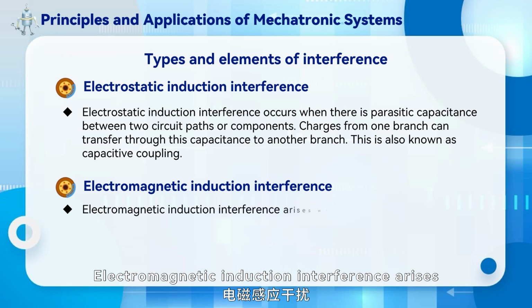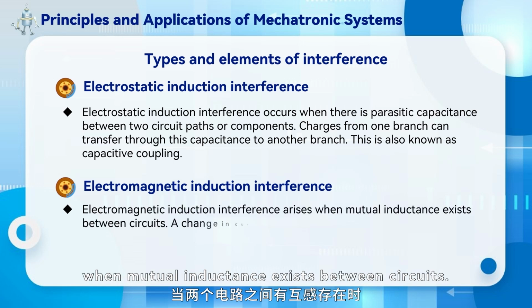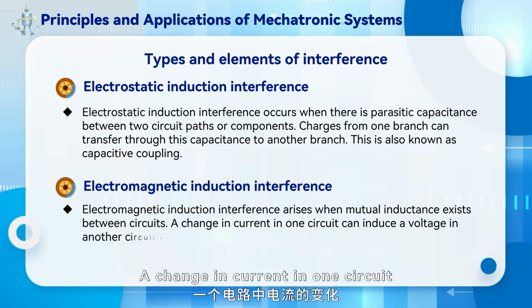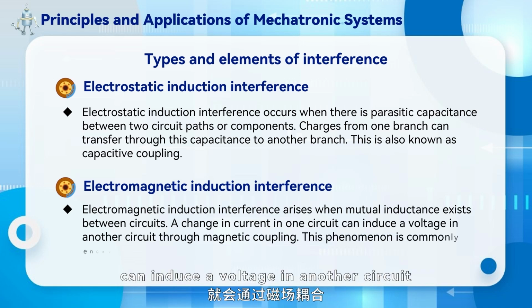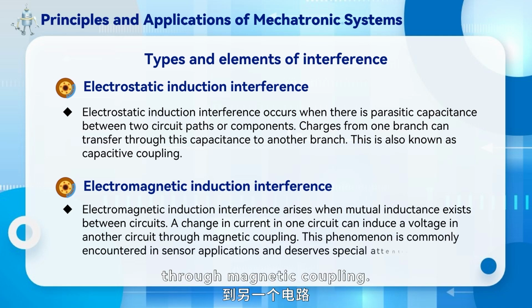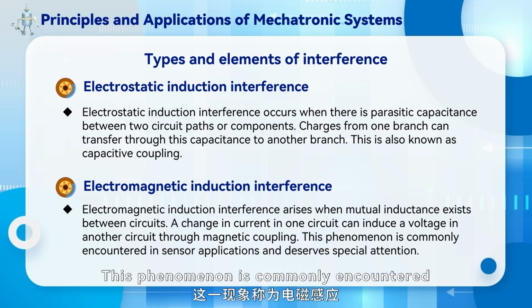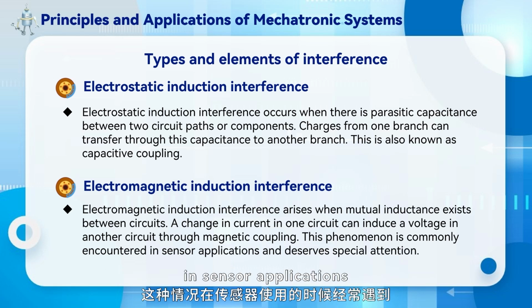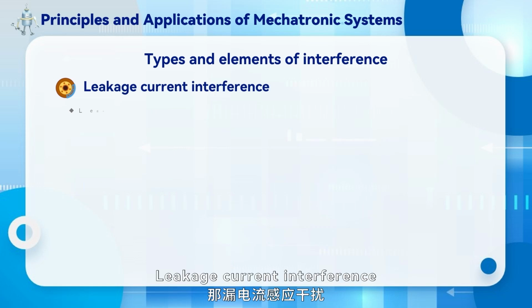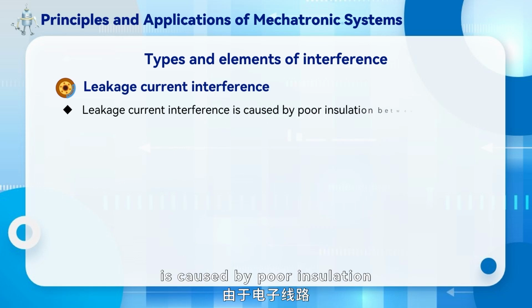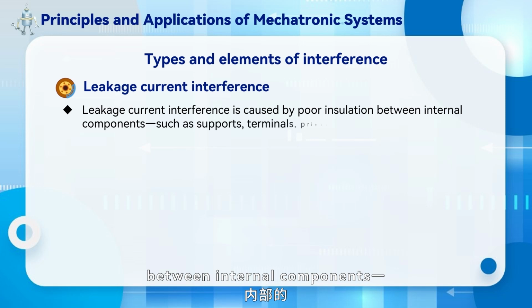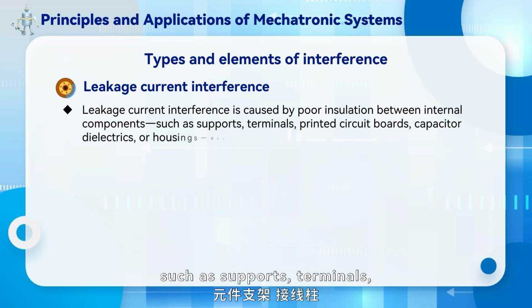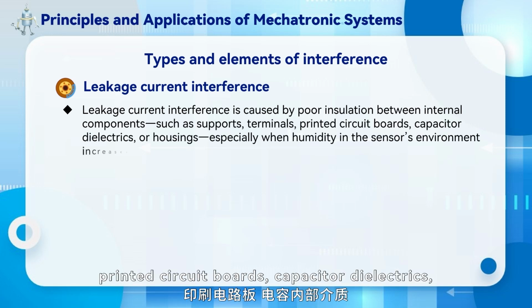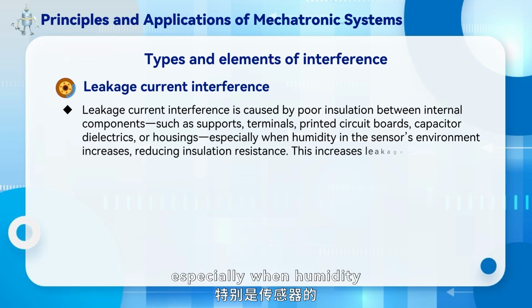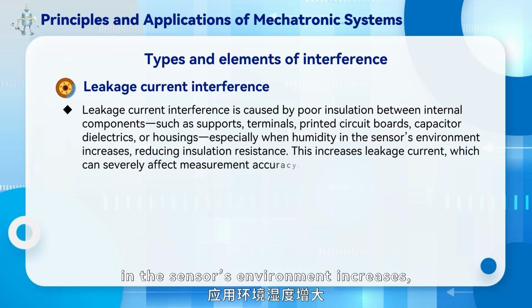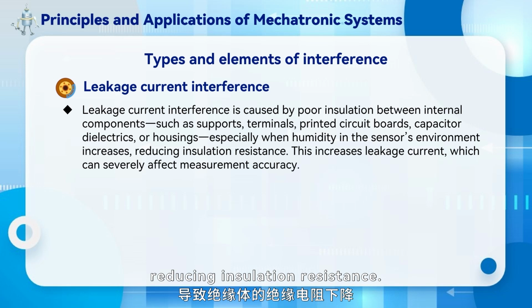Electromagnetic induction interference arises when mutual inductance exists between circuits. A change in current in one circuit can induce a voltage in another circuit through magnetic coupling. This phenomenon is commonly encountered in sensor applications and deserves special attention. Leakage current interference is caused by poor insulation between internal components, such as supports, terminals, printed circuit boards, capacitor dielectrics, or housings, especially when humidity in the sensor's environment increases, reducing insulation resistance.